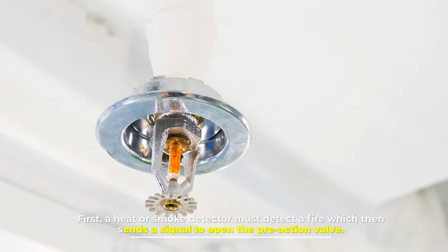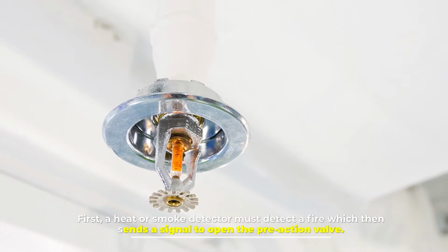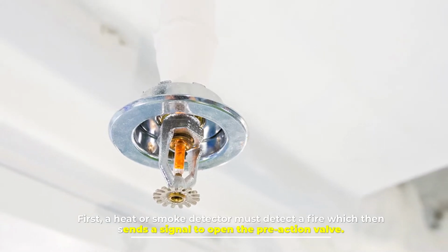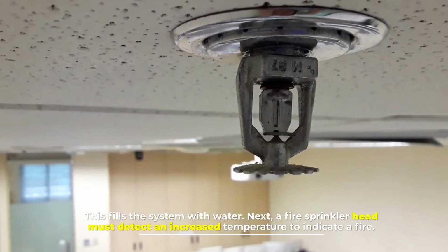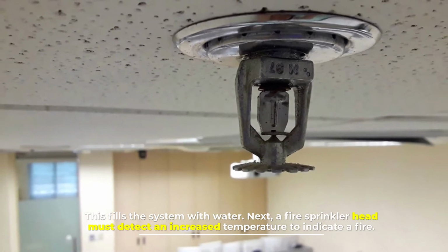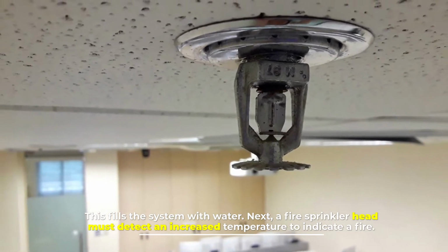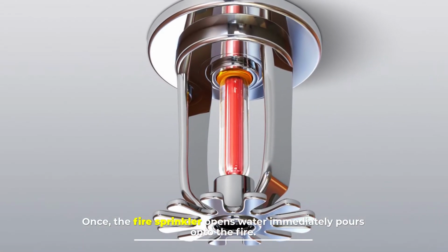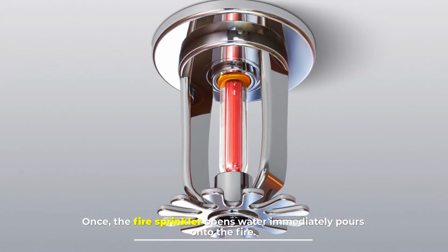First, a heat or smoke detector must detect a fire, which then sends a signal to open the PreAction valve. This fills the system with water. Next, a fire sprinkler head must detect an increased temperature to indicate a fire. Once the fire sprinkler opens, water immediately pours onto the fire.